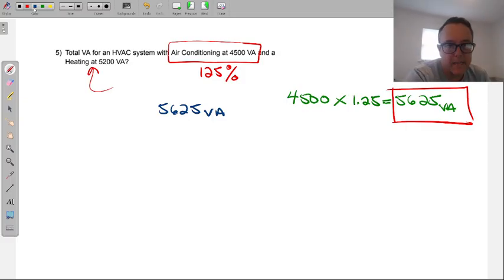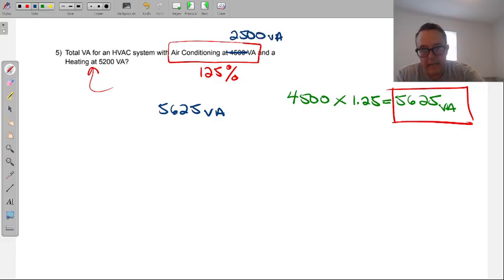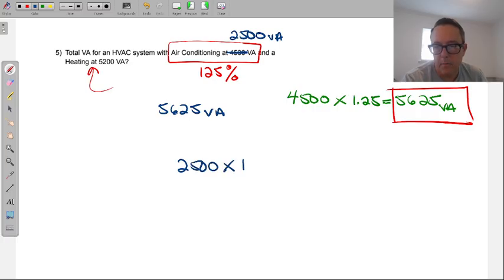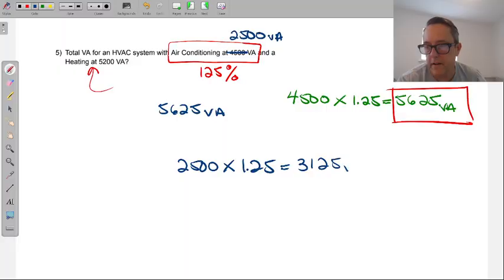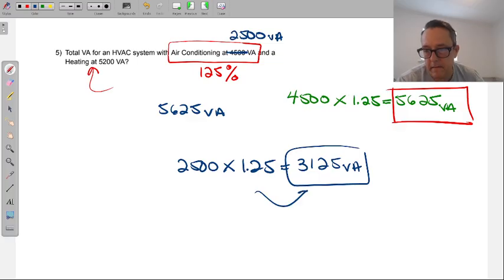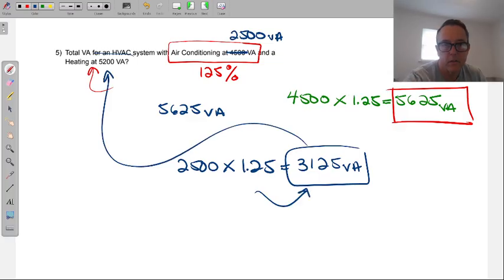All right, let's say, for example, I'm going to use a low enough number that I know the math will work out, 2500 VA. So again, the air conditioning is smaller. So we first bump up the air conditioner by 1.25 and see where that increases us to. And now it only takes us to 3,125 VA. So we've increased it, but we're still smaller than the heater. So we would still go with the heater. It's always going to be the bigger load of the two. But the air conditioner just has to be run through 125%.